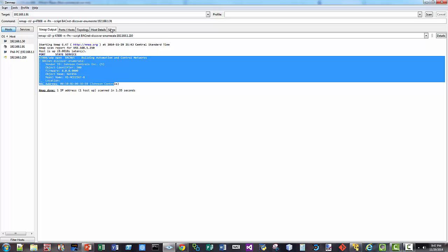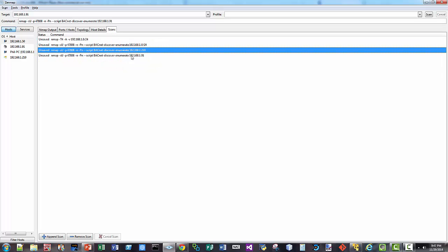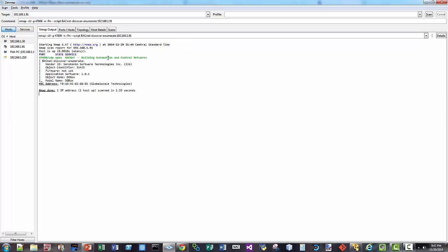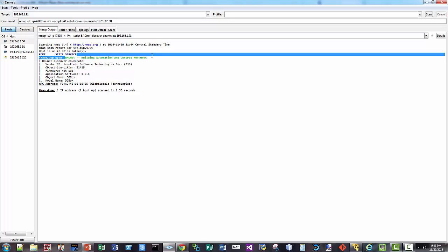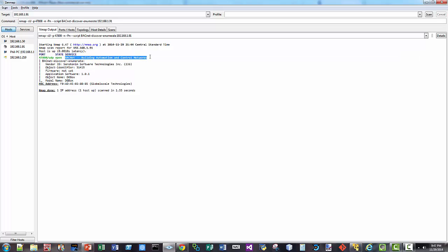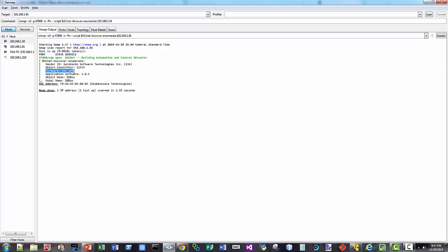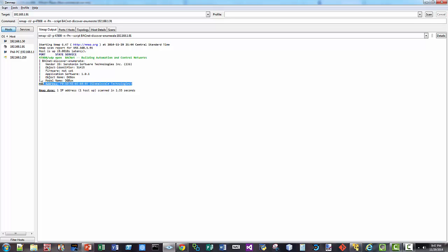So then I go and I do my next scan, which is the dash 91. And I pull the other device. So you can see 47808. It's UDP. It's showing it open. BACnet. Alright, it's telling you what service it is. It's saying, this is the vendor ID. This is the object identifier. It's not saying what firmware it has. Application software. DG Box. That's the software, or that's the model. And object. So those are two things that I have sitting on my network right now.